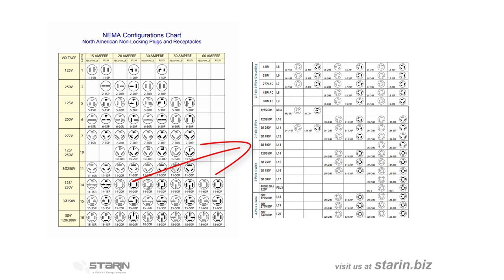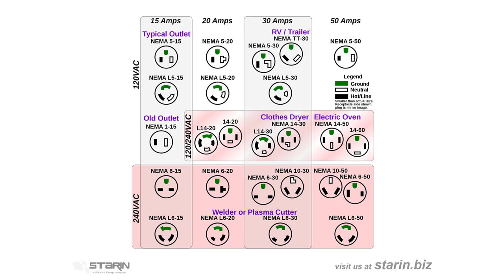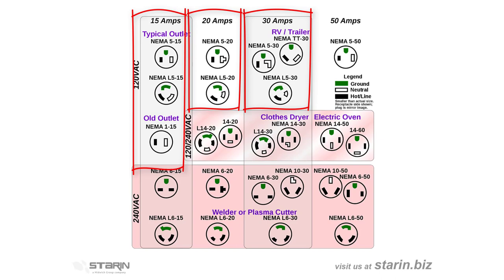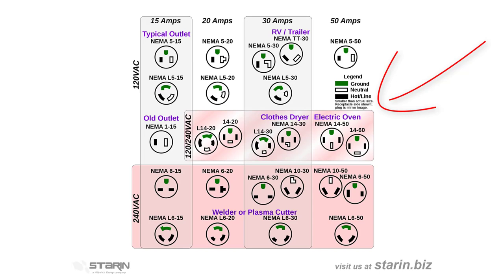The criteria that we need to establish is the maximum current draw of the device. For the sake of this discussion, we divide them into three categories: 15 amp, 20 amp, and 30 amp. The 30 amp connectors are few in Pro-AV and are usually only for high output video projectors and power amplifiers. If you're dealing with large lighting systems, you may get into much greater current requirements, so consult with the EC directly when you get to that point.